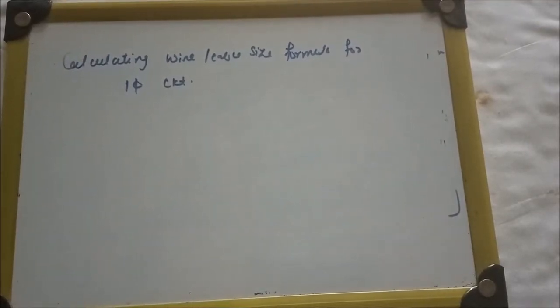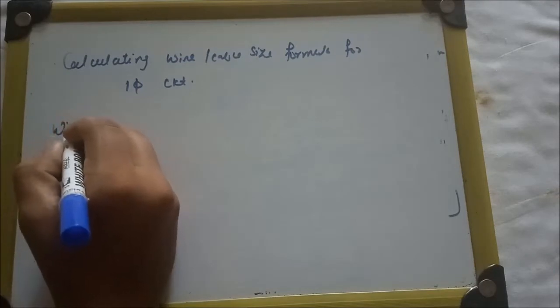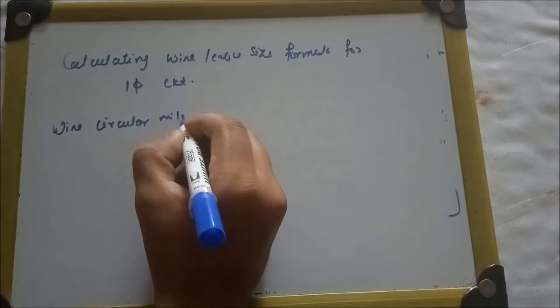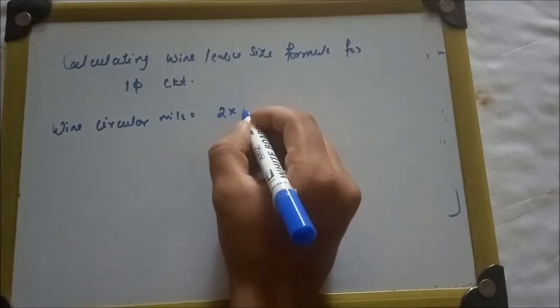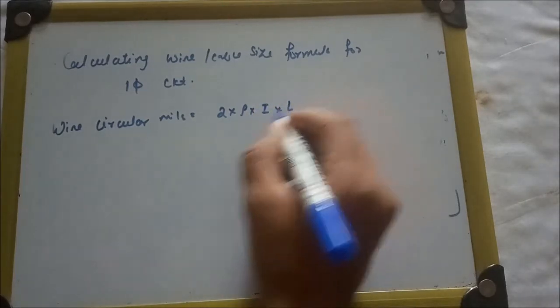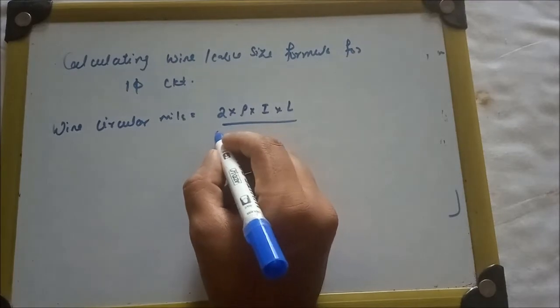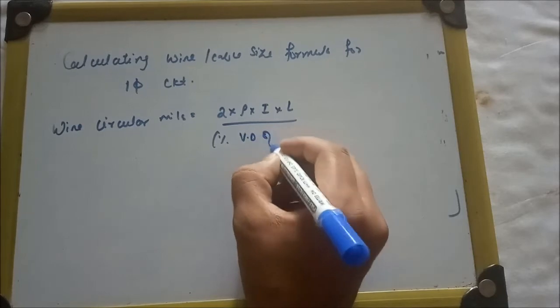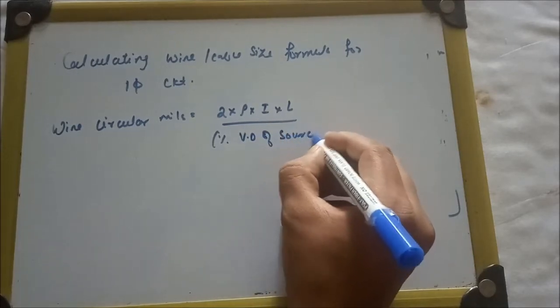Now, what will be the wire or cable size formula for single-phase circuits, which may be copper or aluminum? The formula is given as wire circular mils equals 2 × ρ × I × L divided by percentage voltage drop of source voltage.